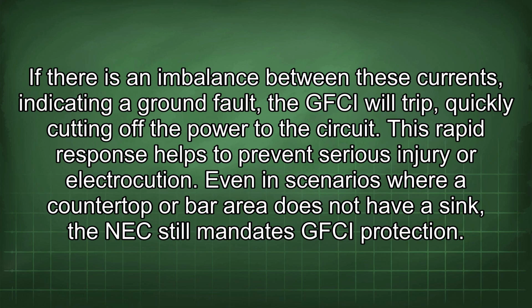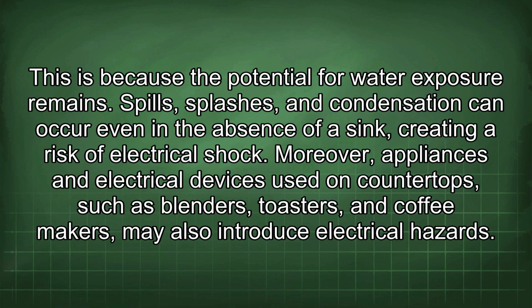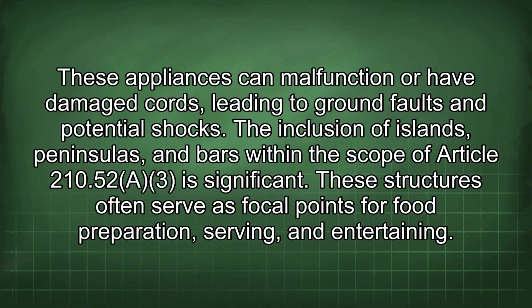Even in scenarios where a countertop or bar area does not have a sink, the NEC still mandates GFCI protection. This is because the potential for water exposure remains. Spills, splashes, and condensation can occur even in the absence of a sink, creating a risk of electrical shock. Moreover, appliances and electrical devices used on countertops, such as blenders, toasters, and coffee makers, may also introduce electrical hazards. These appliances can malfunction or have damaged cords, leading to ground faults and potential shocks.